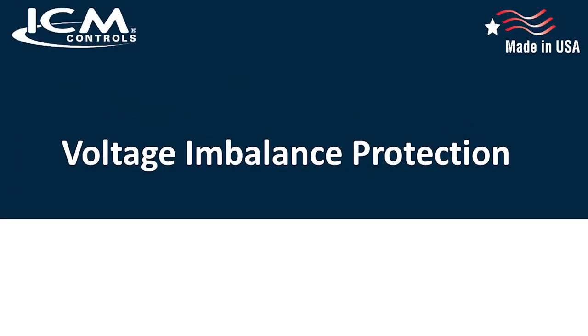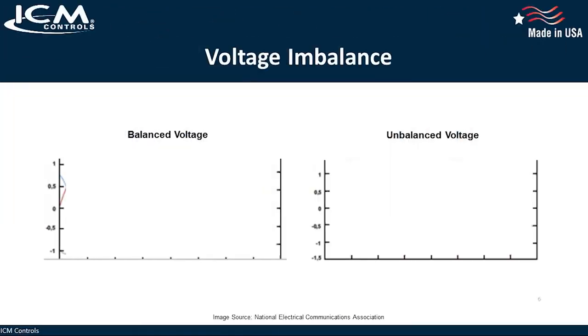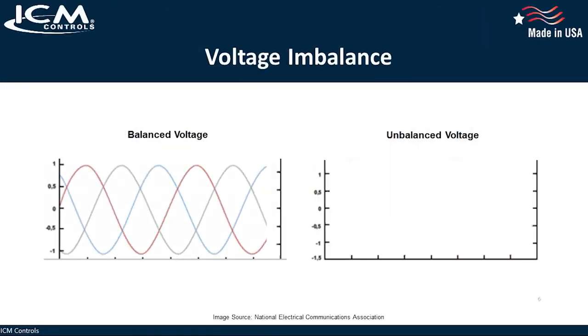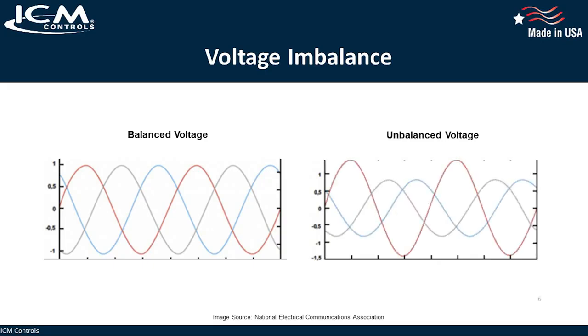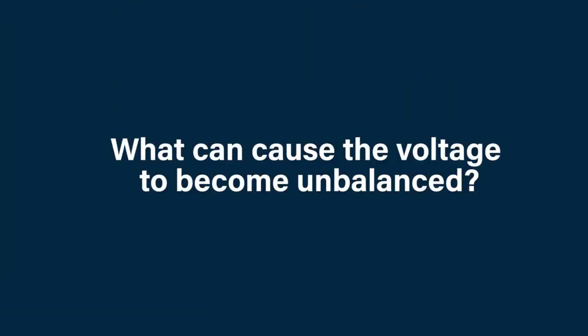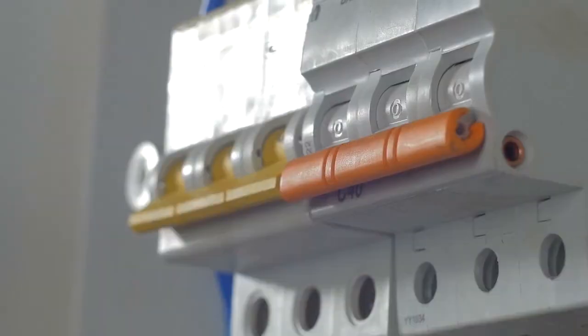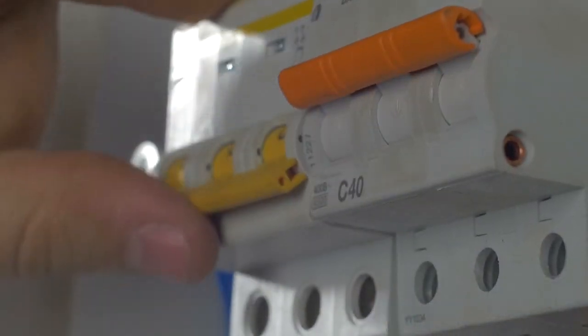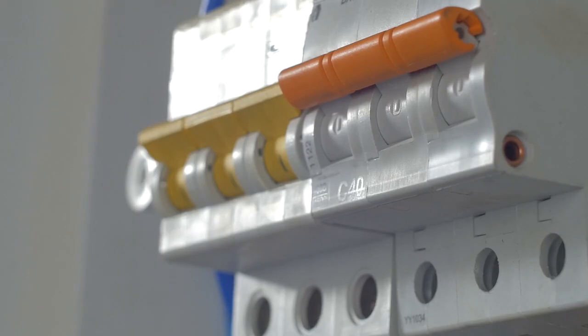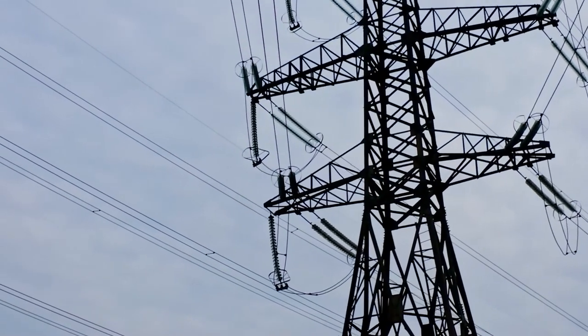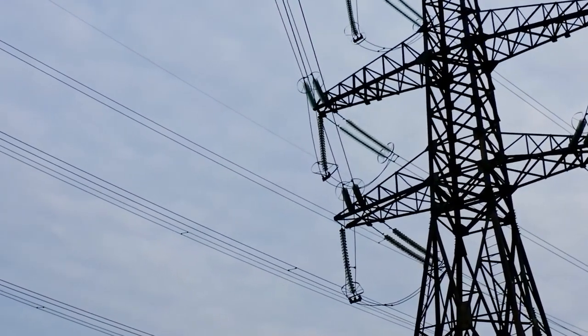Voltage imbalance applies to three-phase systems when one or more of the phases or line voltages become mismatched. Under normal conditions, all three-phase voltages would be identical. When one or more of the phase voltages is unbalanced, you get this. So what can cause the voltage to become unbalanced? It can be something as simple as a blown fuse or a loose connection, or it can come from the source voltage, such as the utility company itself.